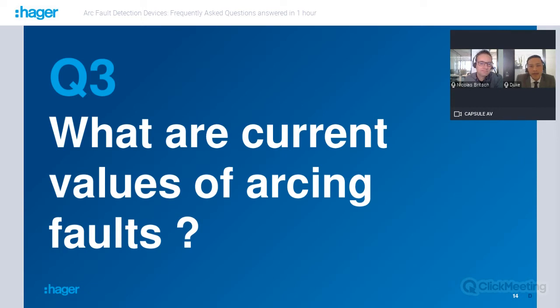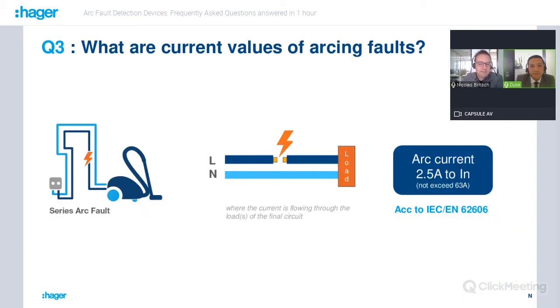Okay, so what are the current values of arcing fault? Can you tell us a little bit further? Yes, of course. First, you have to know that scientific studies have demonstrated that for series arc fault, it's very unlikely to have a start of a fire with current value lower than 2.5 amps. That's why the detection is starting from 2.5 amps and up to the rated current of the device. And this is for series arc fault.